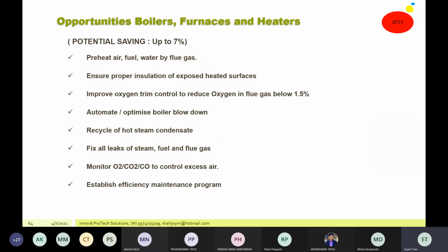What are the opportunities in boilers, furnaces and heaters? Preheat air, fuel or water by flue gases. Ensure proper insulation of exposed heated surfaces. Keep oxygen in flue gas below 1.5%. Automate and optimize boiler blowdown. These are all the areas where energy losses are taking place, and industries are optimizing all these areas so that their energy consumption reduces.